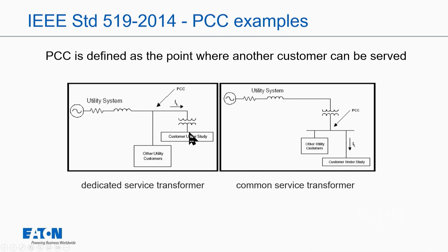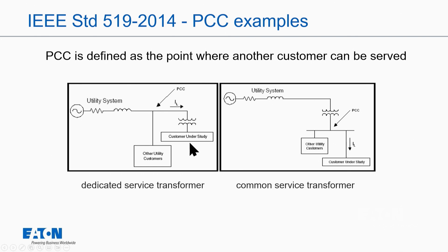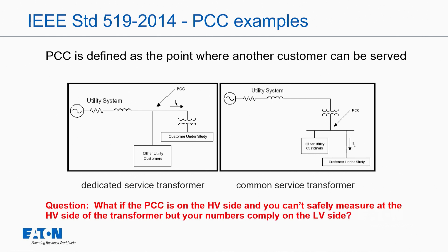If you measure voltage distortion on the secondary and it's okay, then you can be assured that on the primary it's going to be okay, because we're pushing harmonic currents from the load toward the source. The current on both sides of the transformer would be the same from a THD standpoint, minus the third harmonics that could circulate in the delta winding, or if it's a delta zigzag, could come back to the load. If the PCC is on the high side and you can't safely measure there, but your numbers comply on the low voltage side, then you can be assured it's going to be okay.